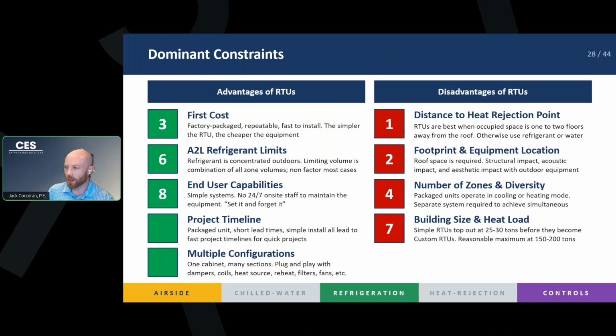Is this a quick project, right? And so a lot of these bigger systems are going to be more complicated on install time, right? Maybe a VRF system running all that refrigerant piping is going to take too much time, or you don't have time to run chilled water, or wait for long lead times of big condensing units or chillers. Rooftop units are typically in stock. They are shipped to site quickly, and it's just ductwork in the space, right? It's not a complicated pressurized system that needs to be tested and you're going to have an easy time installing packaged rooftop units. So if you need a quick turnaround on your project, rooftop units are a pretty good way to go.